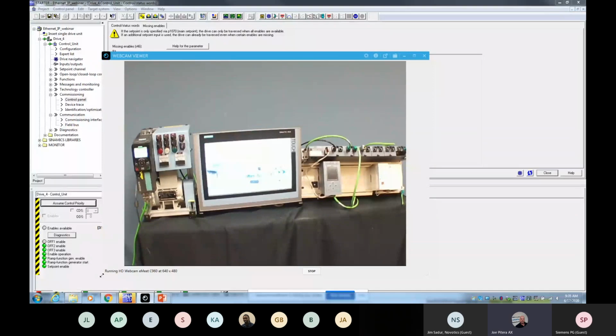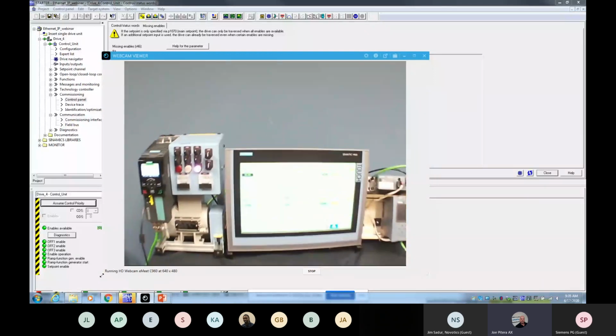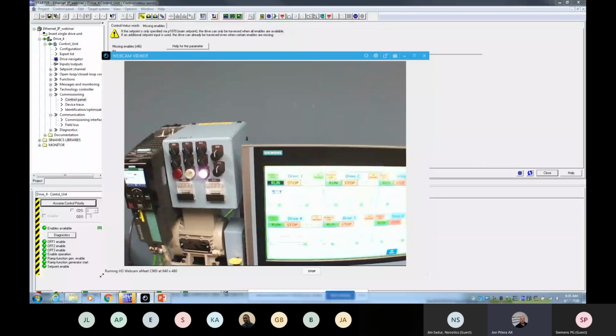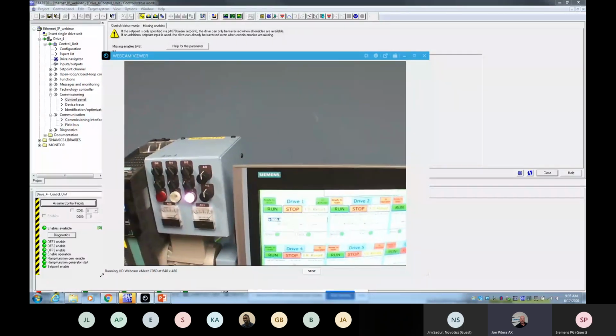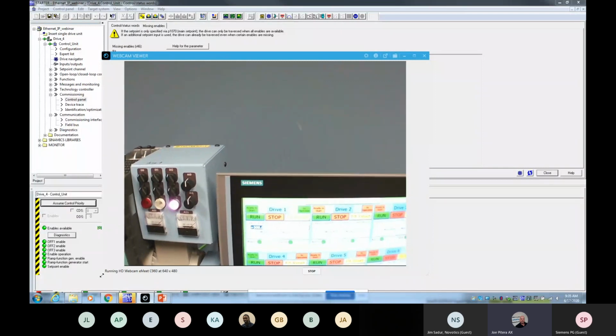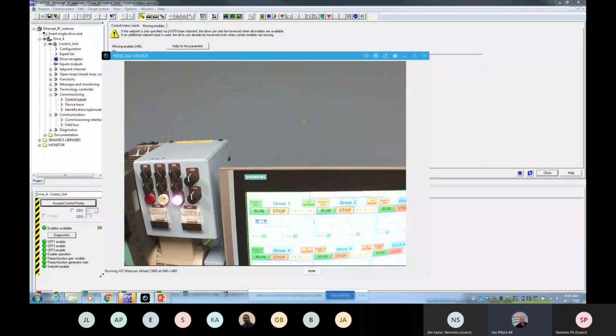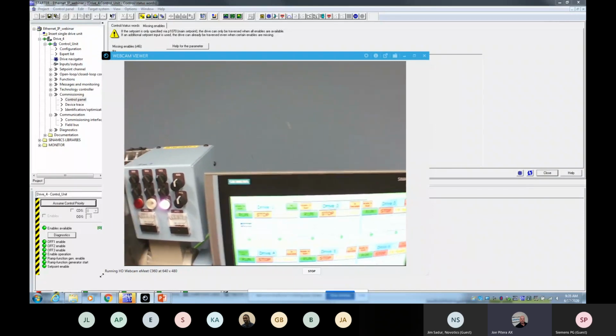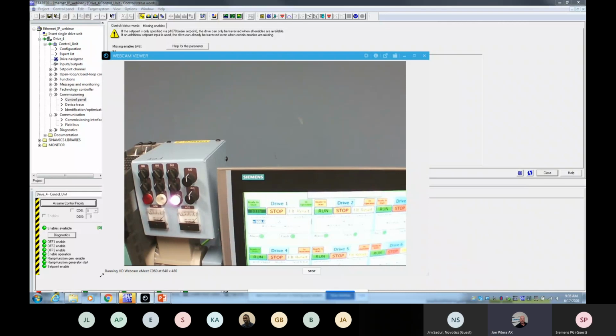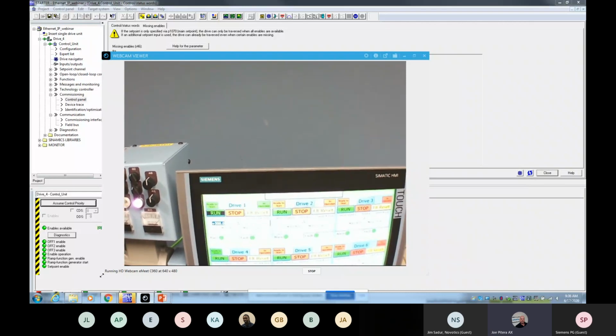And since this was already pre-configured to run Profinet, I should be able to start the drive from the HMI, give it a speed set point, and zoom in to the screen here. And you should be able to hopefully see that the system is running. It's showing the motor amps, motor torque, and the motor actual speed. Although the clarity isn't the greatest, I apologize.